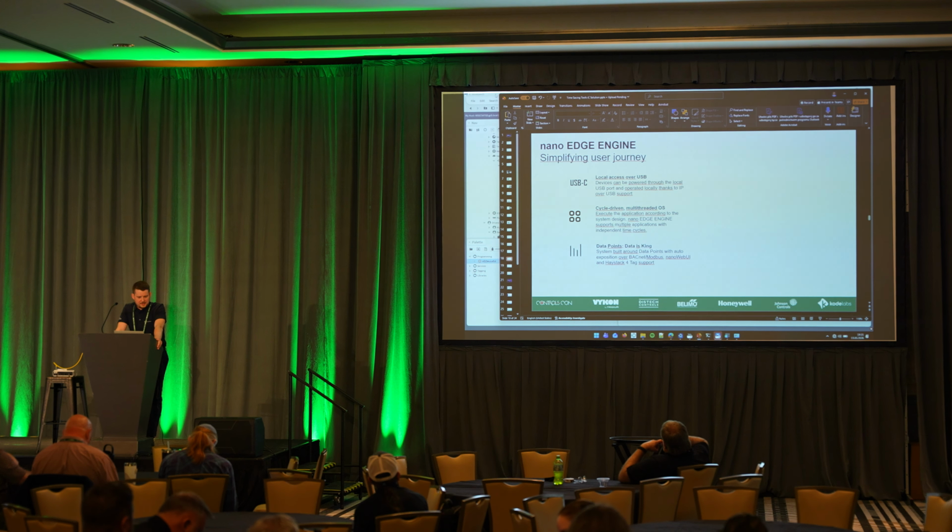And yeah, we can create our first application here. So there is one already. So if we connect to this controller, we can create a new one. We can click OK. Let's call it, so this is our zones application. So we will integrate some VAVs to control their set points during this demo. So we have now two applications. They'll both be running in a 500 millisecond cycle.